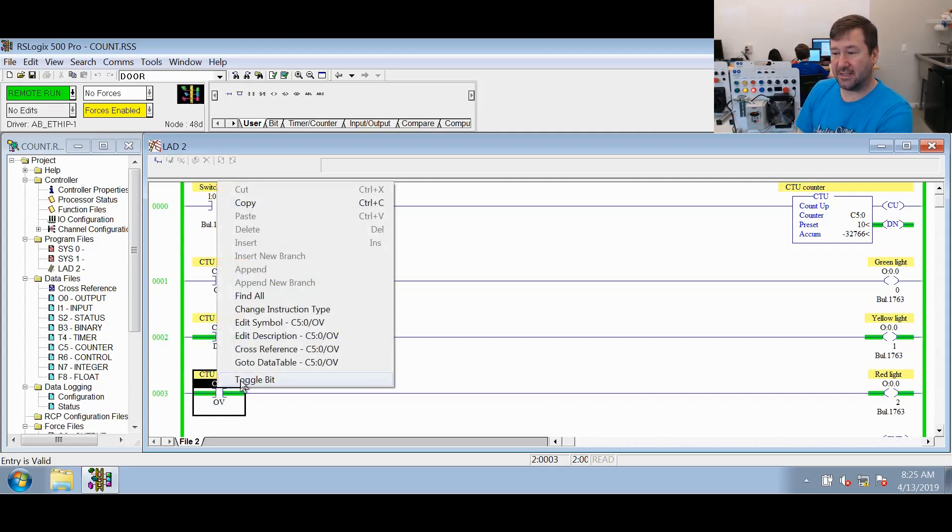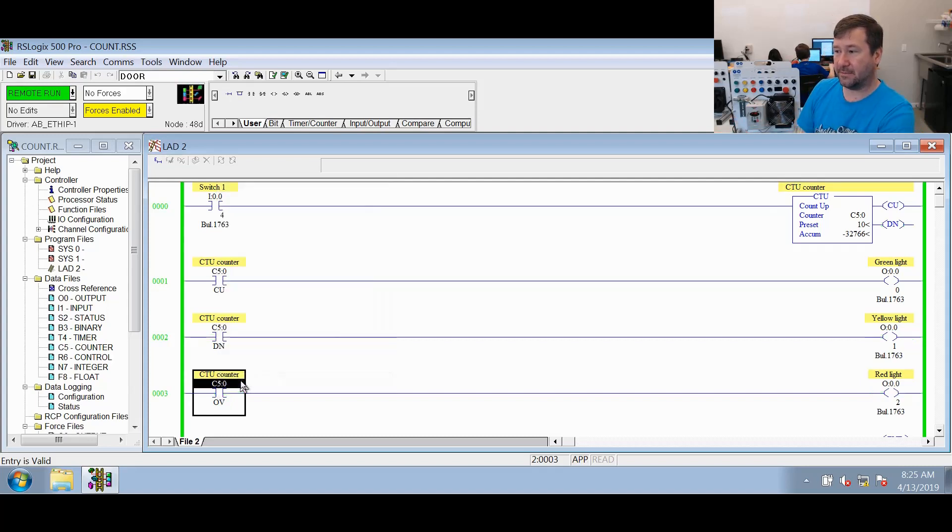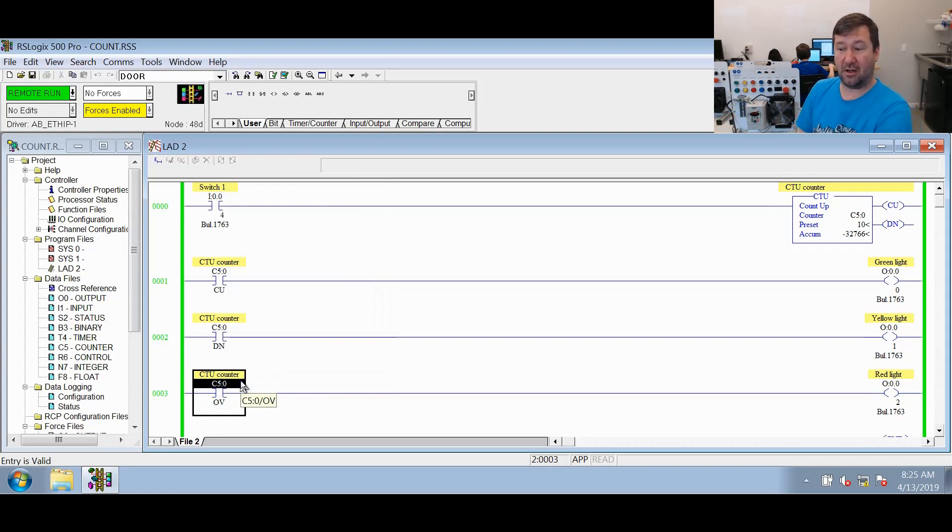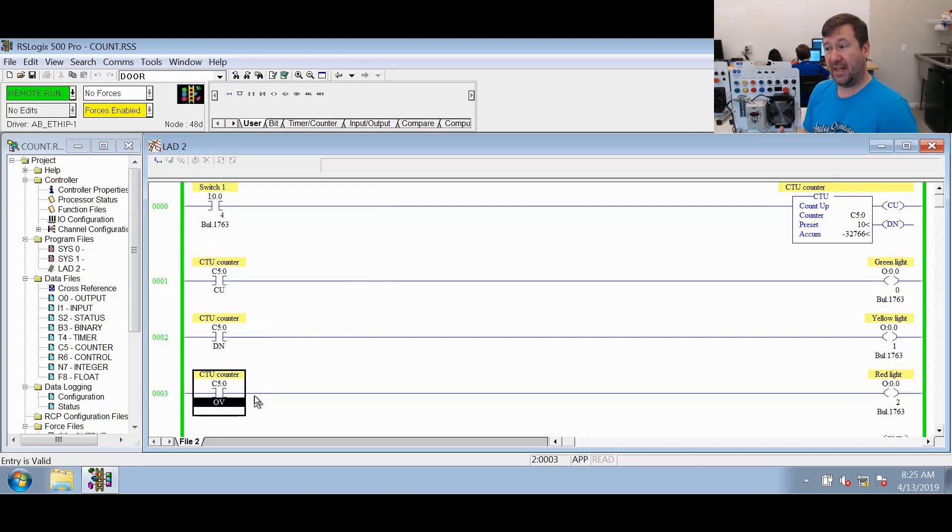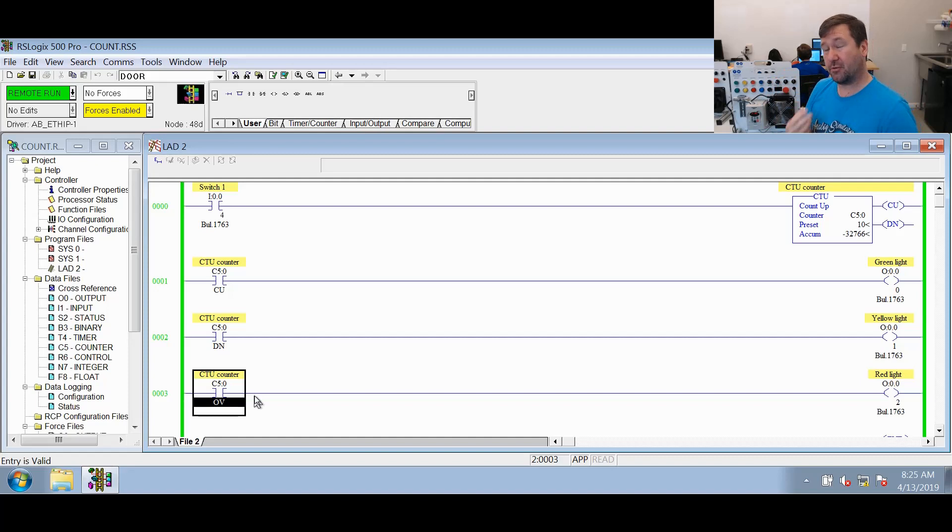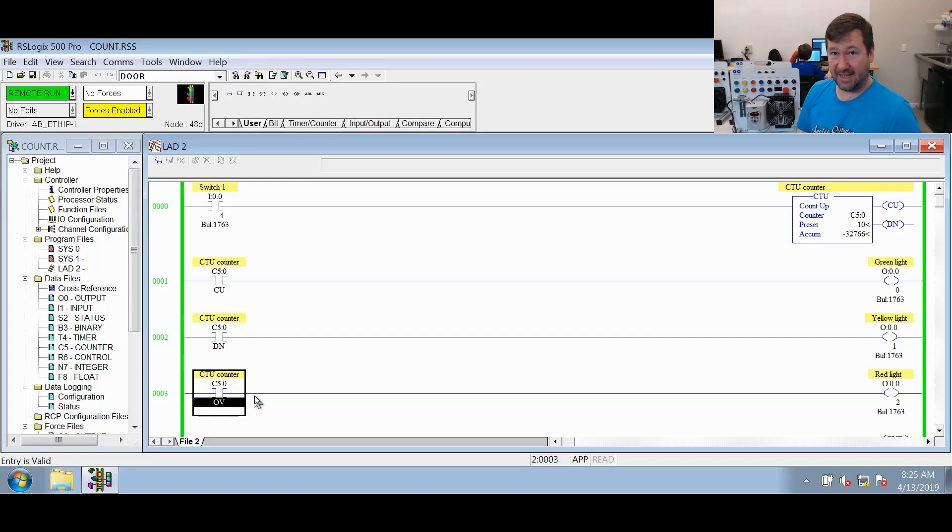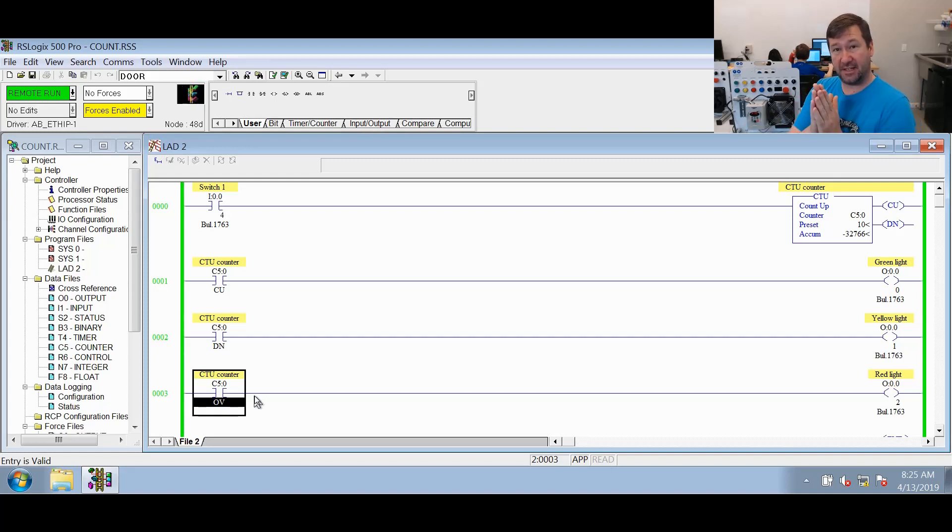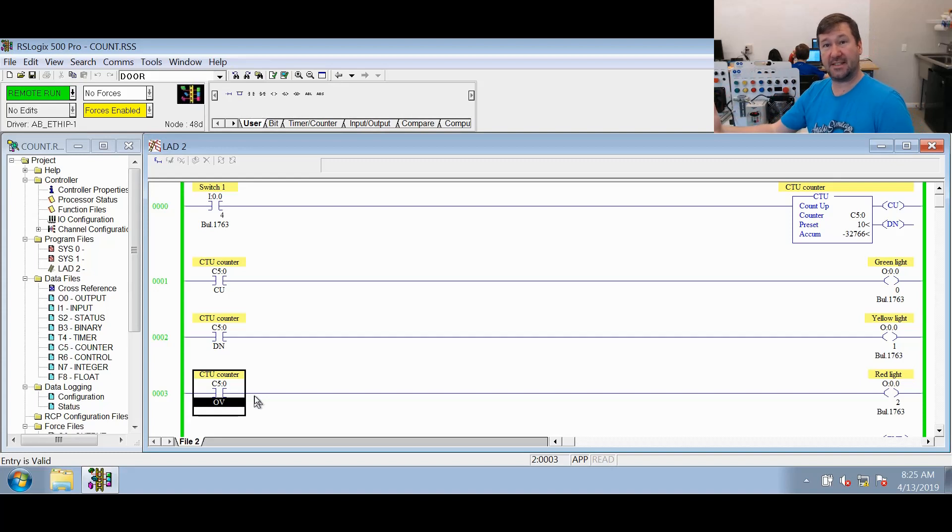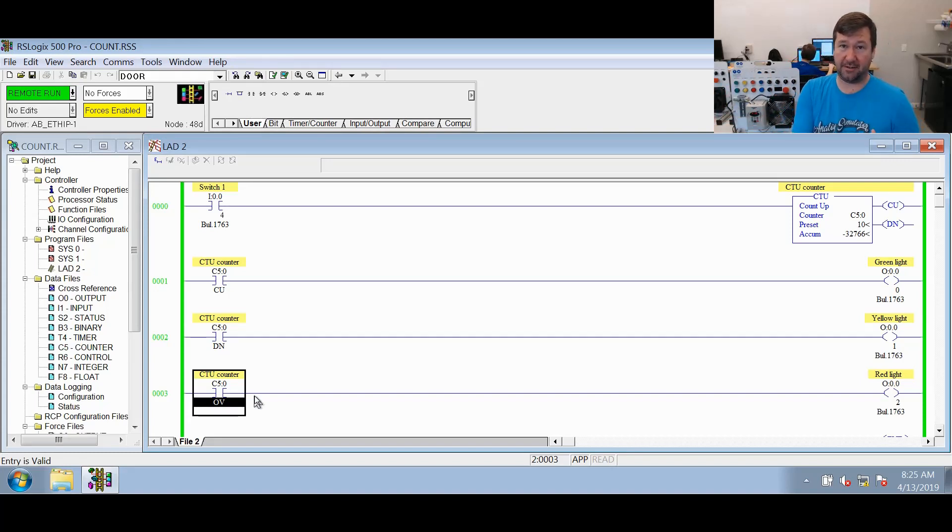So if we right click this and toggle it, you see the done bit goes off. So really, it is that the accumulated value is greater than or equal to the preset, or the overflow bit is set. And then the overflow means that it has made that transition from 32,767 to a negative 32,768.